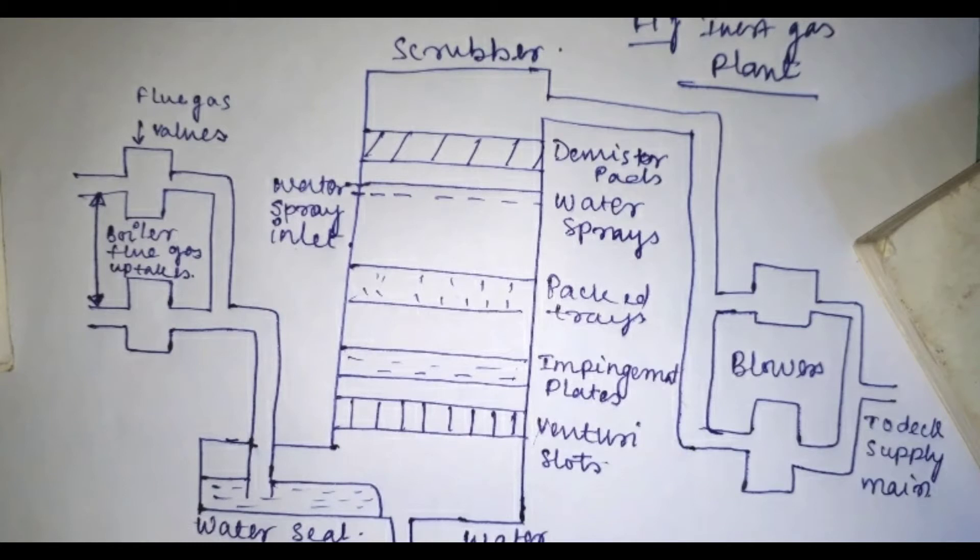Demister trays, which consist of polypropylene mattresses, are located at the top of the tower to remove water droplets from the gas. The sea water which cleans the gas becomes acidic and is led overboard from the bottom of the scrubber by corrosion-resistant piping. Last is a blower. These are electric motor-driven centrifugal blowers which deliver the clean cool inert gas to the cargo tanks via the distribution system.